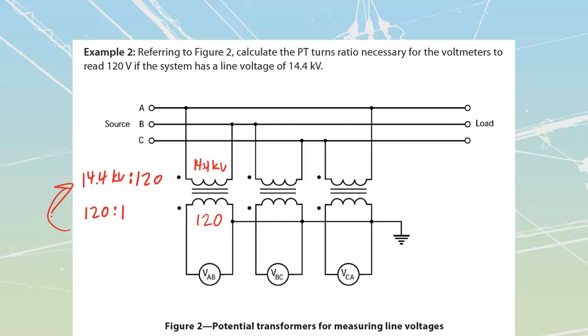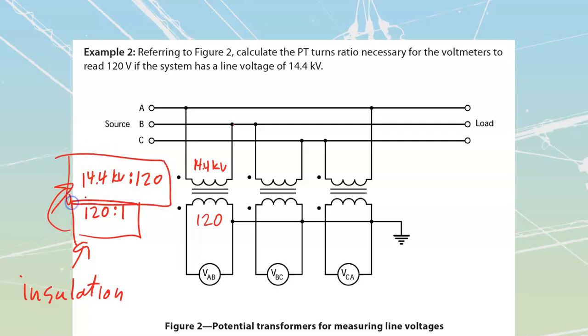This is why we like to see these ratings, that they're actually going to be 14.4 to 120, because if I just look at 120 to 1, that doesn't tell me anything about how good my insulation is on there. You know, is this insulation only good for 600 volts, and we're just doing a 120 to 1 ratio, or is the insulation going to be good for 10,000 volts? Is it going to be good for 500,000 volts? That's why we like to see these ratios written out like that, because first of all, it tells us that it's a PT, and secondly, it tells us the size of the system we can safely utilize this on.